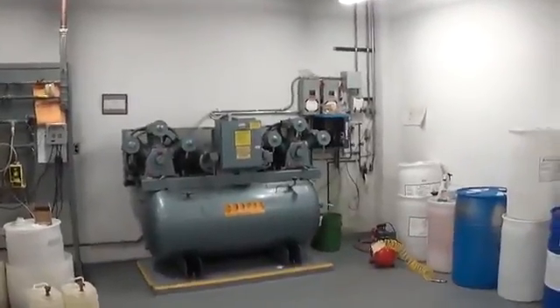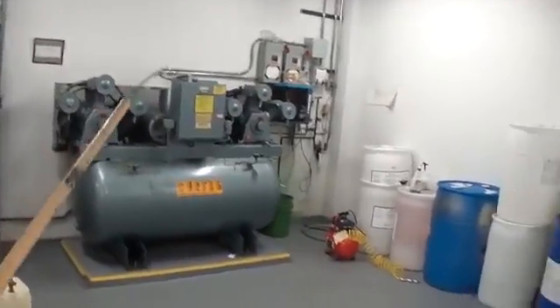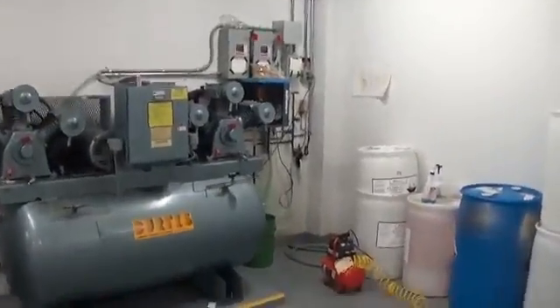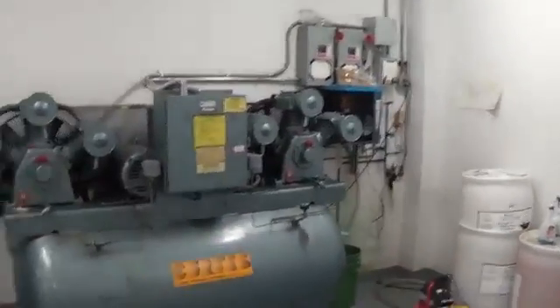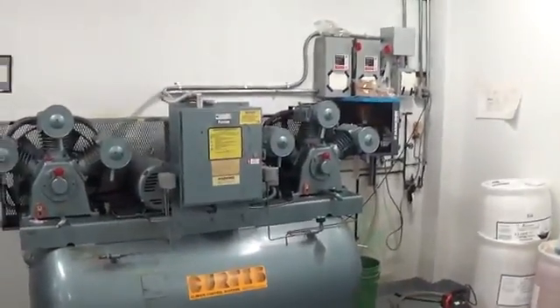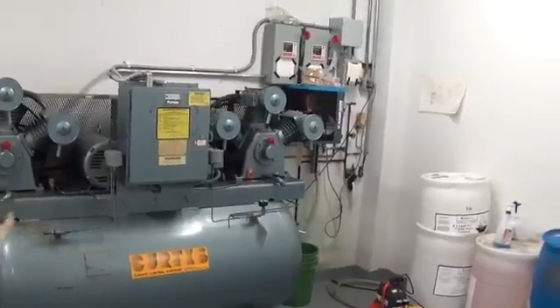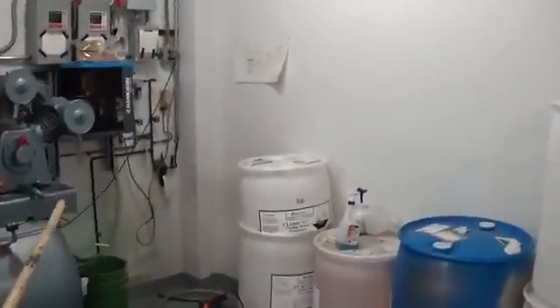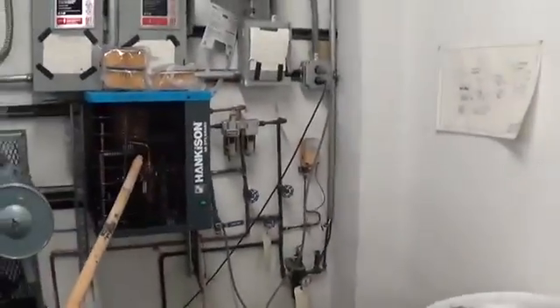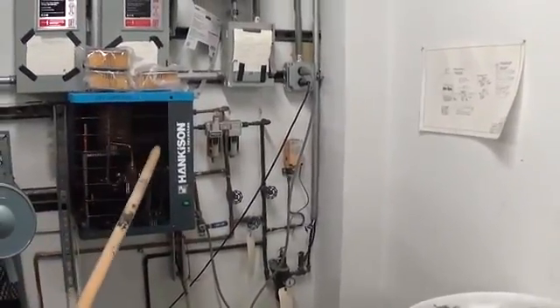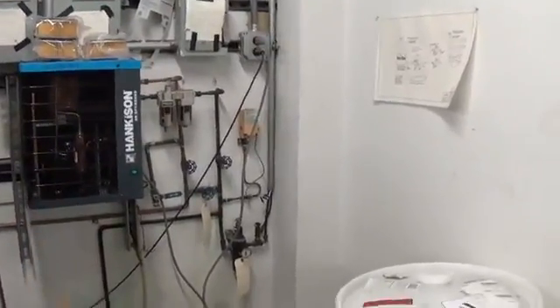So with the air valves, we have to make air. So we have a large air compressor here, which makes air for the chiller plant. As you can see, that is an old air compressor, but it's once more kept in immaculate condition by this crew here. To keep the air nice and dry, an enemy in pneumatics is moisture, so we have an air dryer, which is basically a refrigeration unit that dries the air leaving the compressor. Also removes some oil.